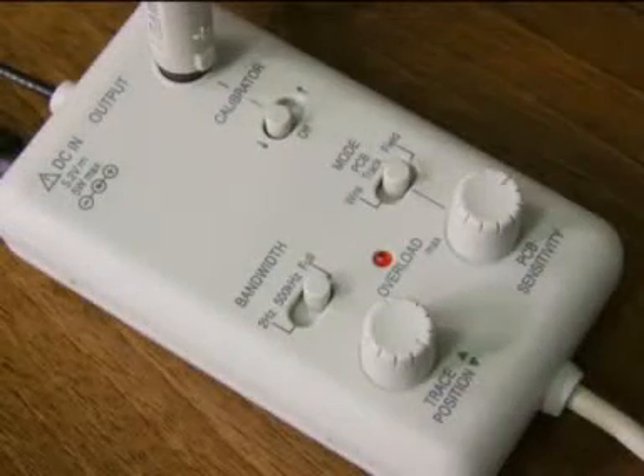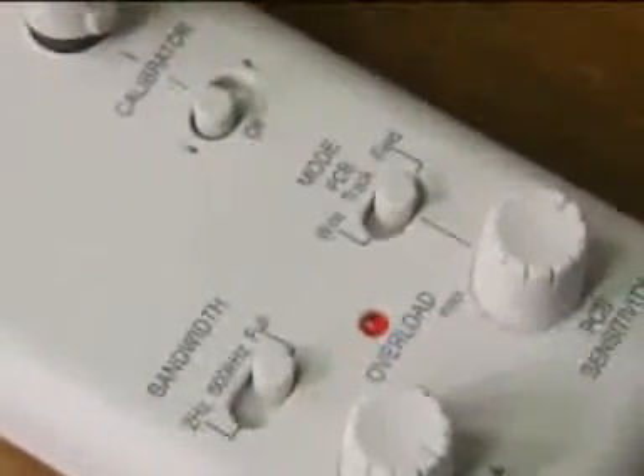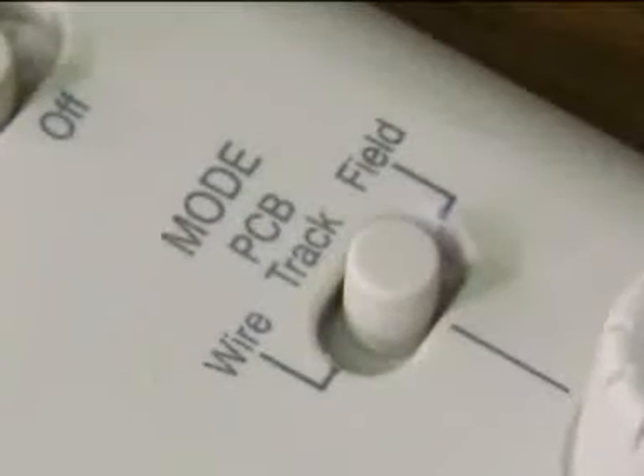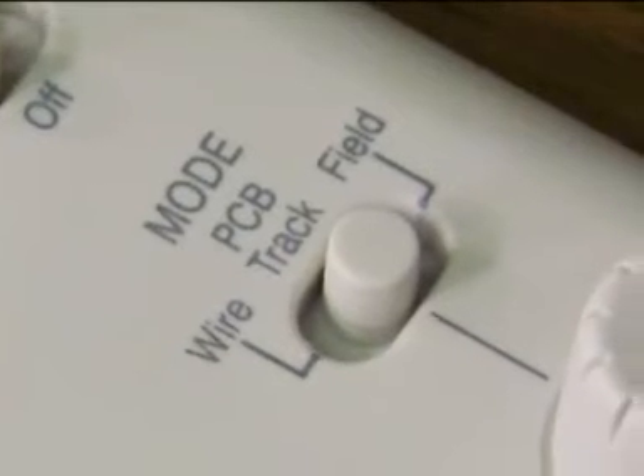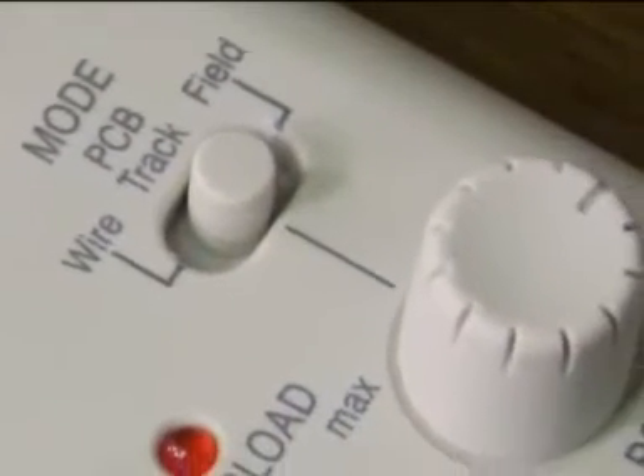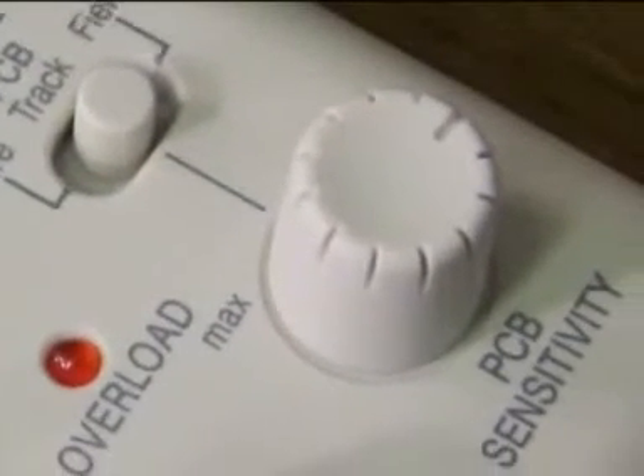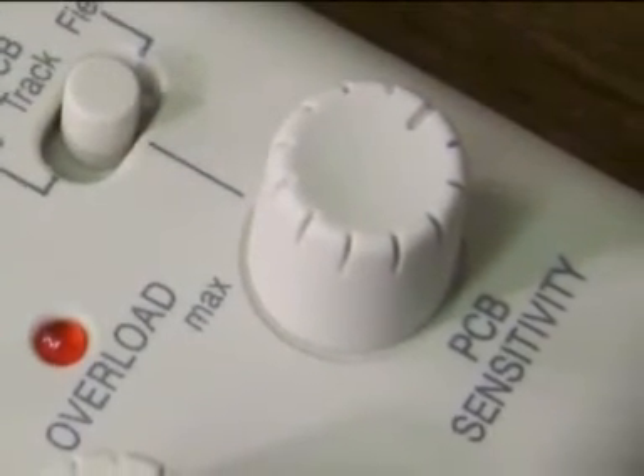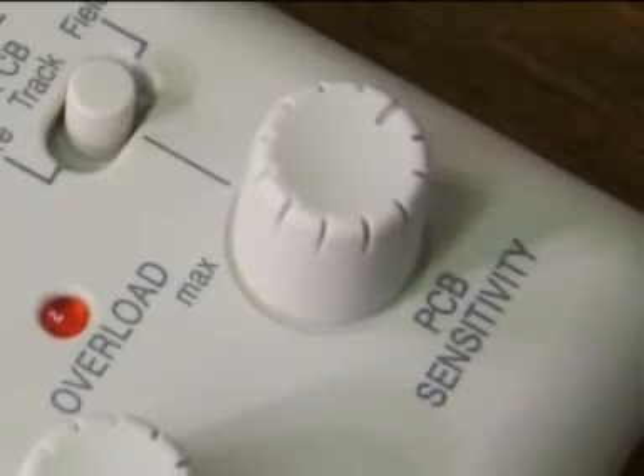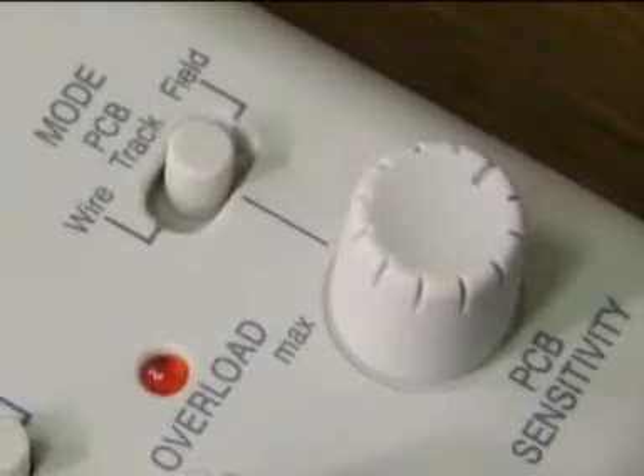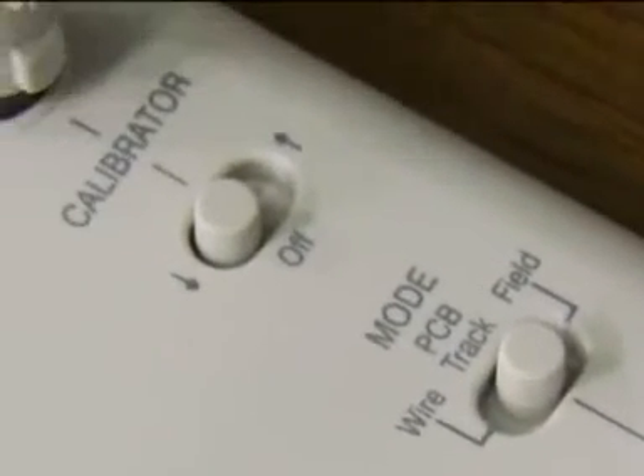So now let's look at the base box. There are 3 switches and 2 knobs. The mode switch is marked PCB track, field or wire. You set wire mode when you use the clip-on toroid to measure the current in a wire or cable. Below the mode switch is the sensitivity control, which is only active in PCB track mode and is used in conjunction with the calibrator to compensate for different widths of PCB track.